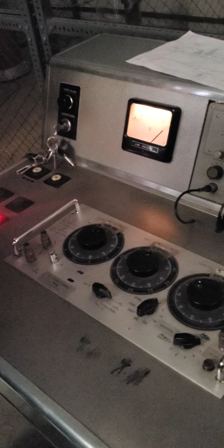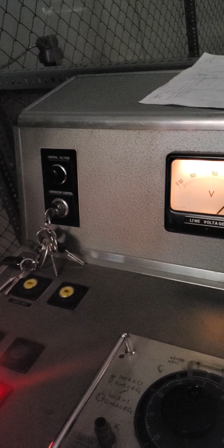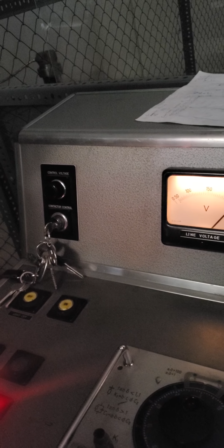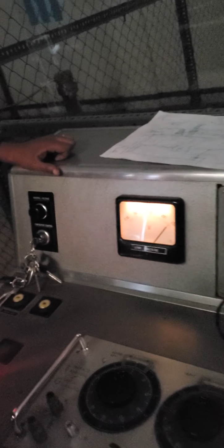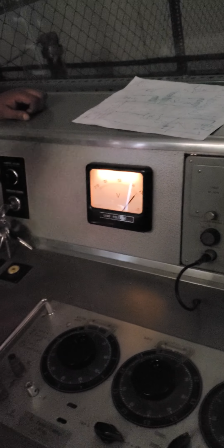Okay, so this we can open. This is primary, this is secondary. Here we are measuring the voltage, around 200, around 235. One division represents 10 volts, whereas the other represents 5 volts. So this is the incoming voltage from the source side, and this becomes the input for the primary of the autotransformer.